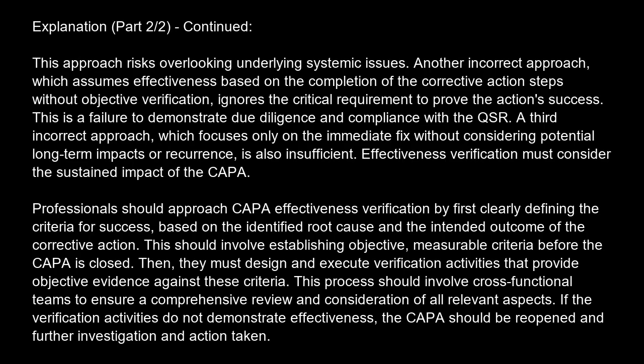Another incorrect approach, which assumes effectiveness based on the completion of the corrective action steps without objective verification, ignores the critical requirement to prove the action's success. This is a failure to demonstrate due diligence and compliance with the QSR. A third incorrect approach, which focuses only on the immediate fix without considering potential long-term impacts or recurrence, is also insufficient. Effectiveness verification must consider the sustained impact of the CAPA.